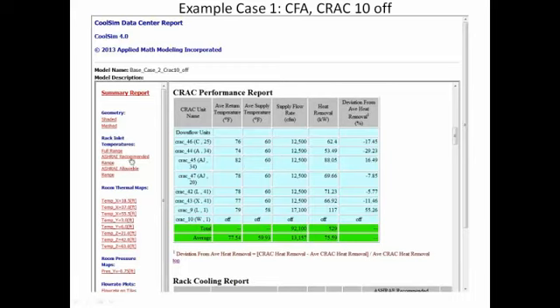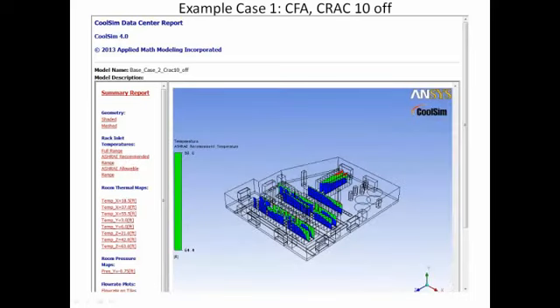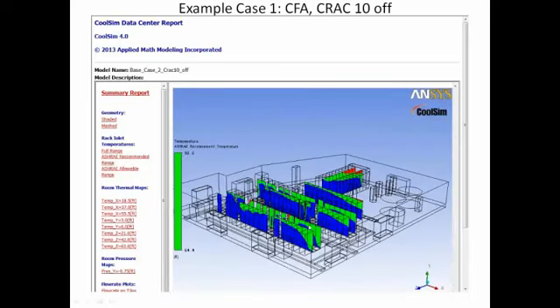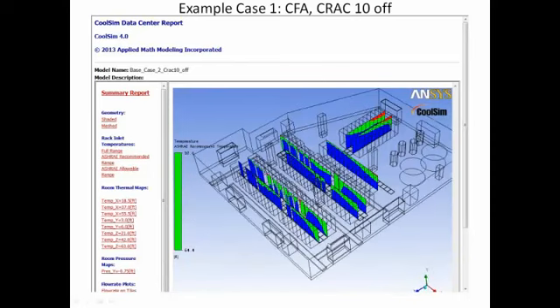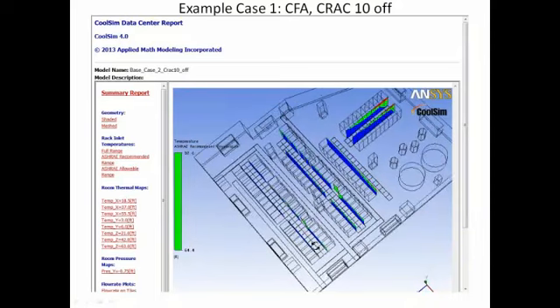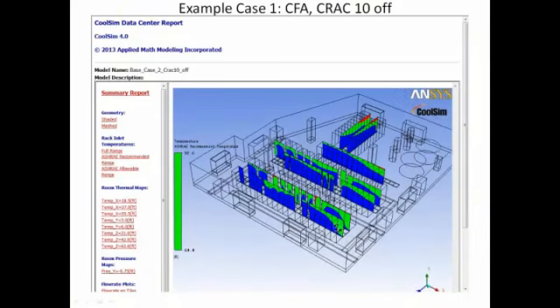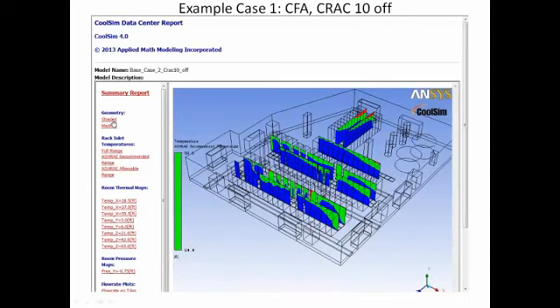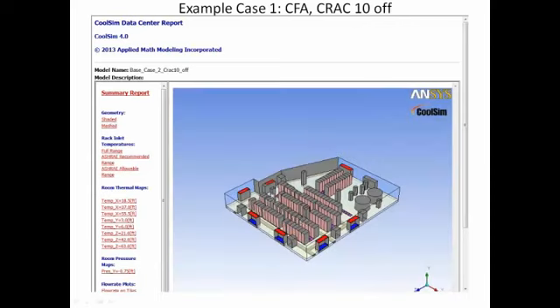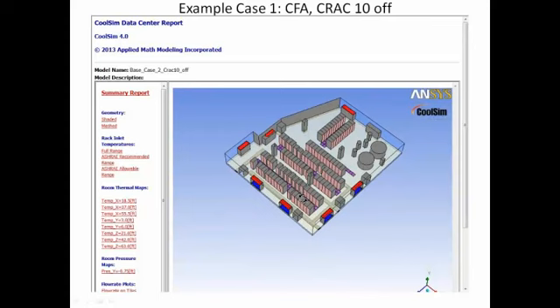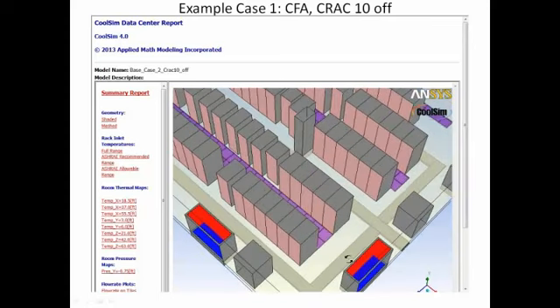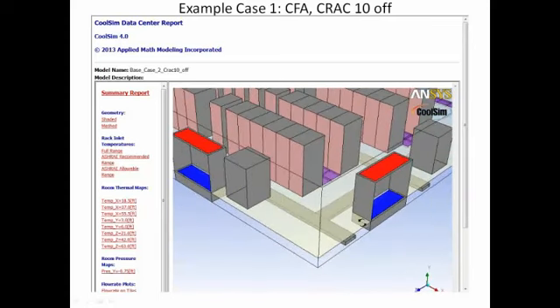Now if I take a look at my recommended plots here, you see I'm not in trouble at all in this region. This region is the section here that I'm most worried about. This is the CRAC unit here that's causing me the most pain because it's close to these. Let's go back and look at it in a shaded view for a minute, and I'll show you. It's close to the CRAC, and whenever you're close to the CRAC, you have very high velocity air coming out, and these have turning vanes on them. So very high velocity coming out, and it's hard for the air to make this corner right here, Magnus, right? Air doesn't bend well. It doesn't want to.